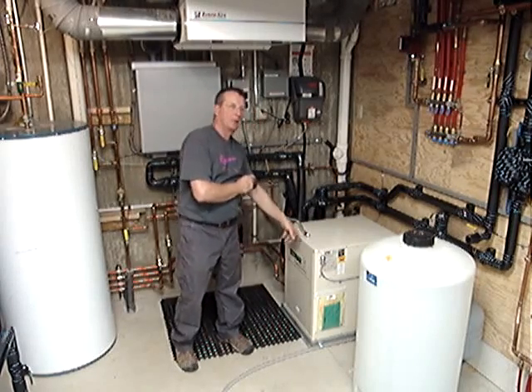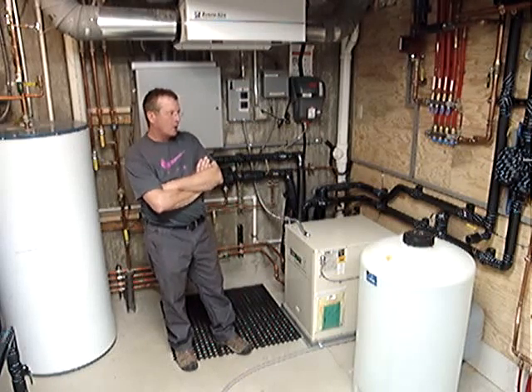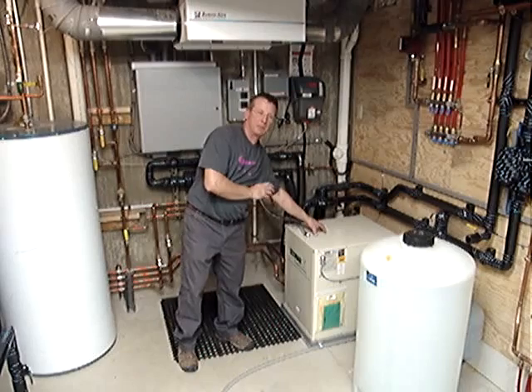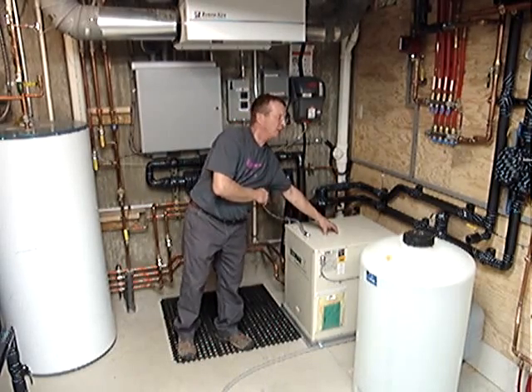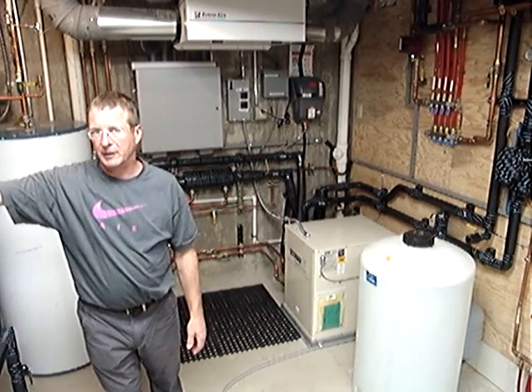Each well has 500 feet of tube and it equates to about a 5-ton loop field. This is a 5-ton heat pump.